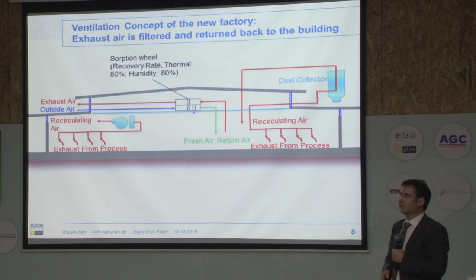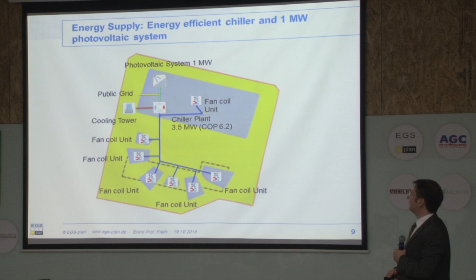Yeah, this is the energy supply concept of the factory. We have a centralized chiller plant with a very high efficiency, with a COP value of 6.2. The cold water is distributed by a district cooling system on the site, and then additionally we have as an energy source a photovoltaic system with a power of 1 megawatt. The problem currently in Thailand is that we don't have a feed-in tariff, which means you cannot produce more electricity than you need on site, and therefore we had to design the PV system so that it never produces more electricity than the factory consumes.